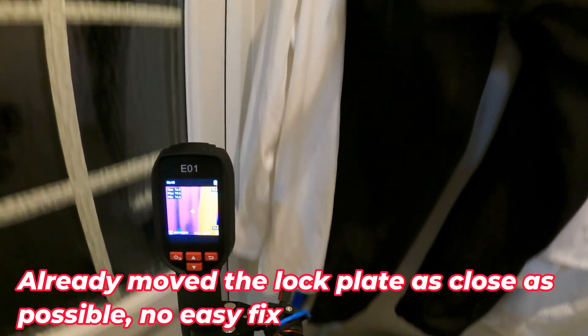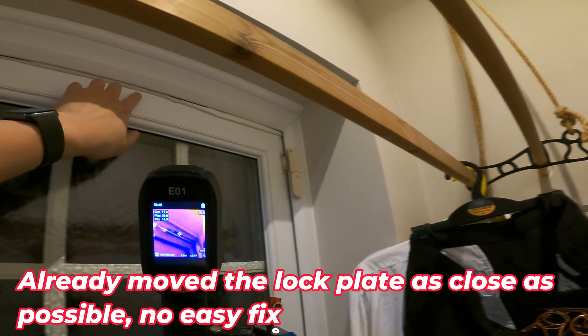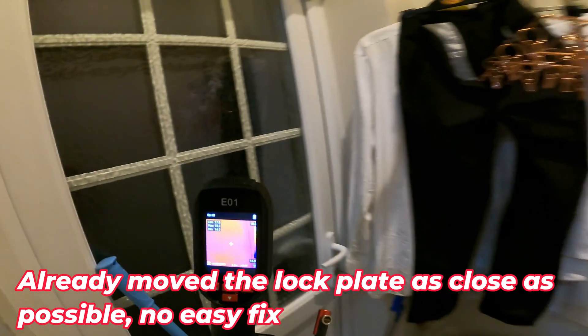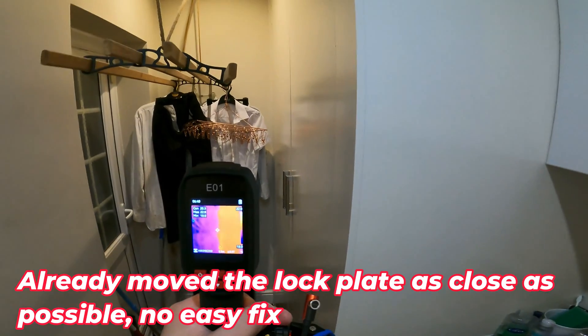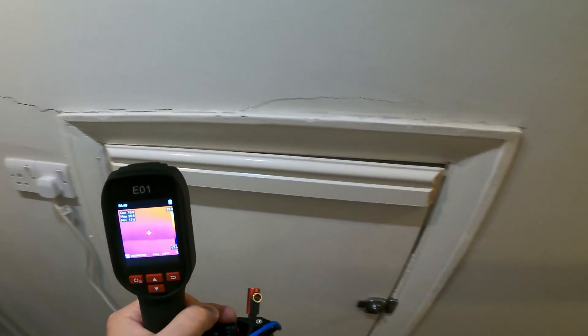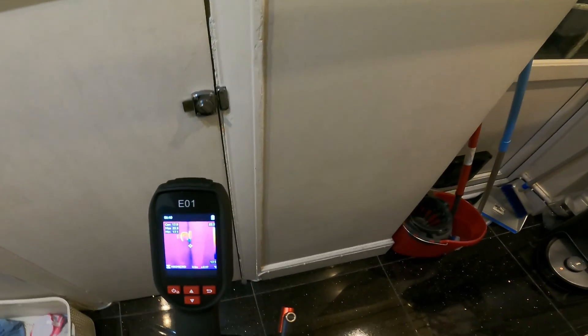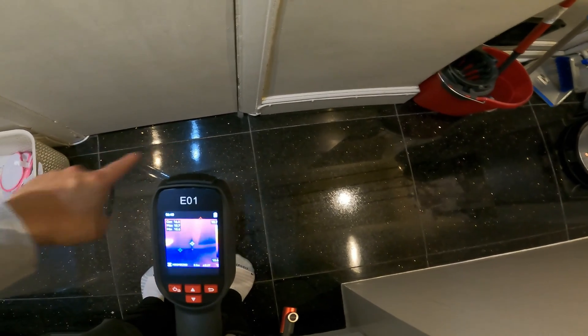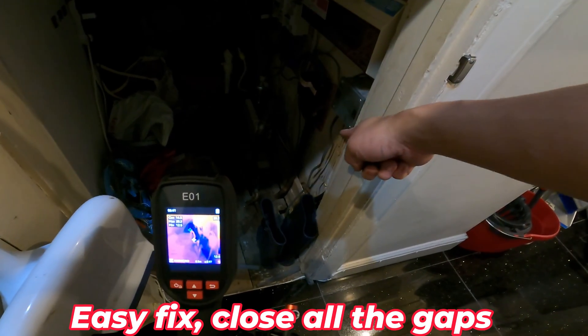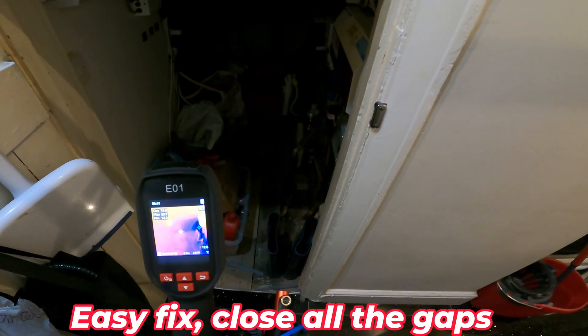And the door doesn't look closed properly either. You can see a blue spot there. We already attempted to seal it with some foam but we're not doing a very good job — there's massive air coming in here. Most of the time you don't feel it because the boiler is right there, but literally we're just heating up the air. Under the staircase, you can see a bit of blue at this corner. There's a cold spot there, and it's not surprising because that wall is actually outside. The cold air is coming through the floorboards and up here.